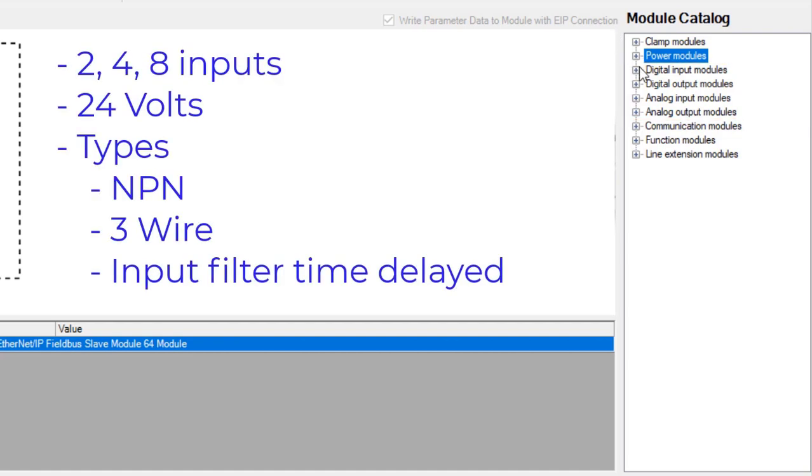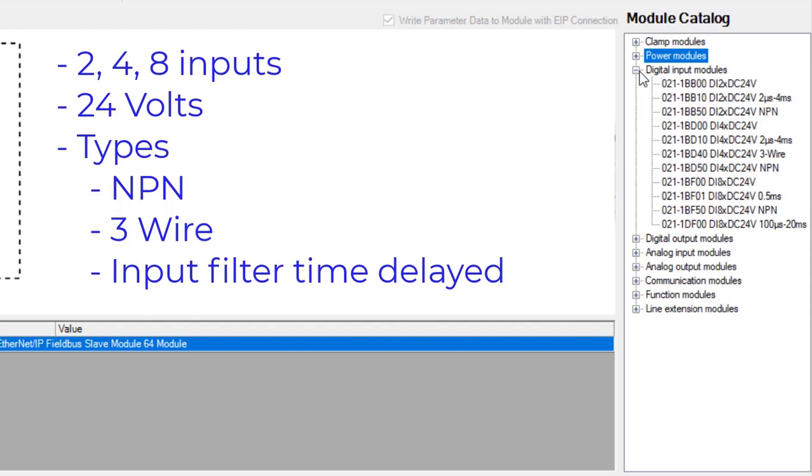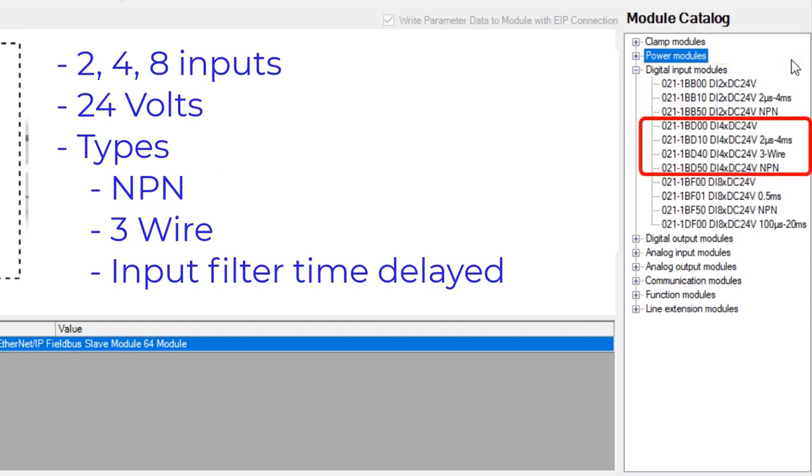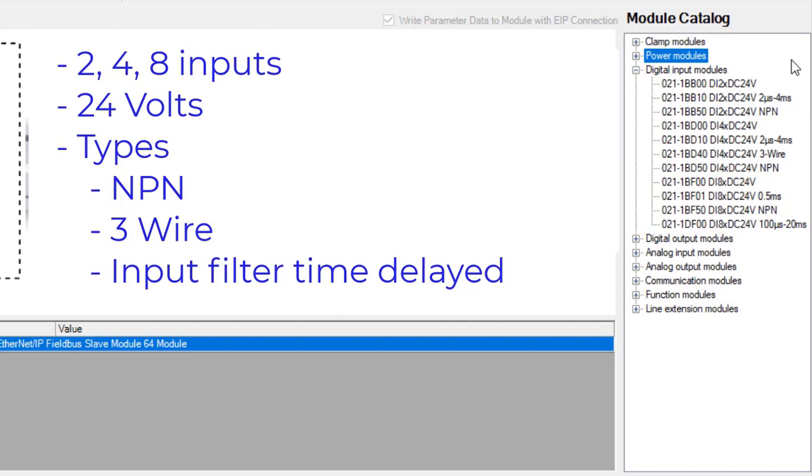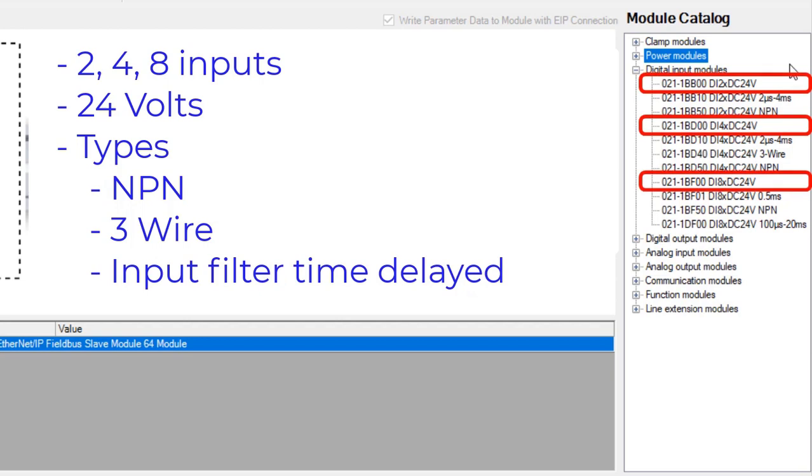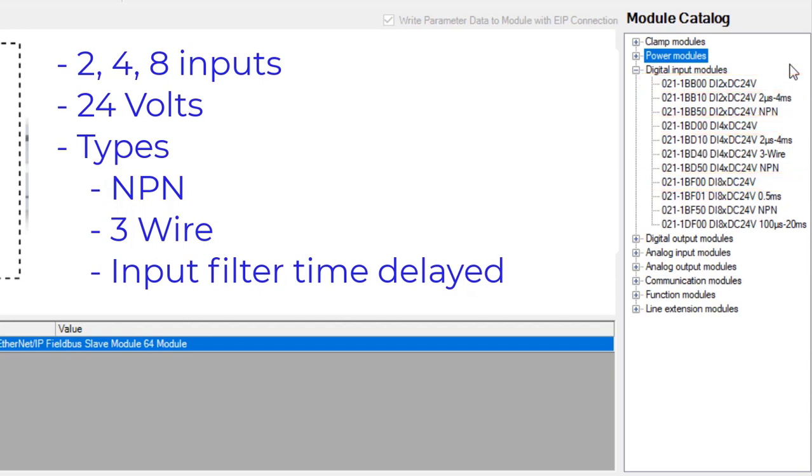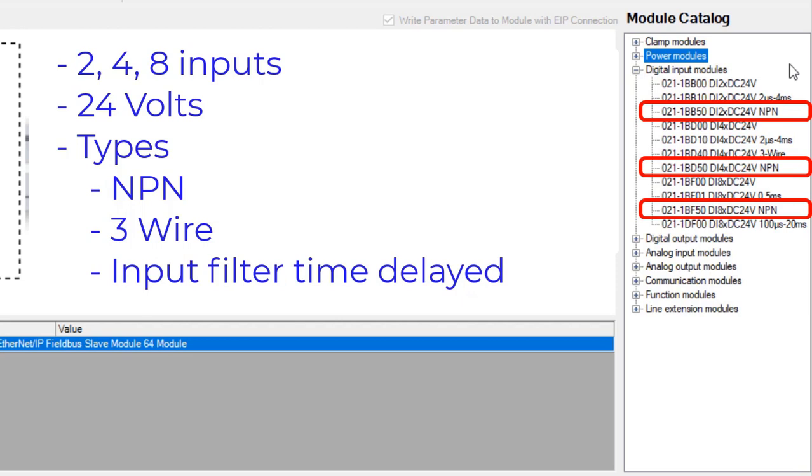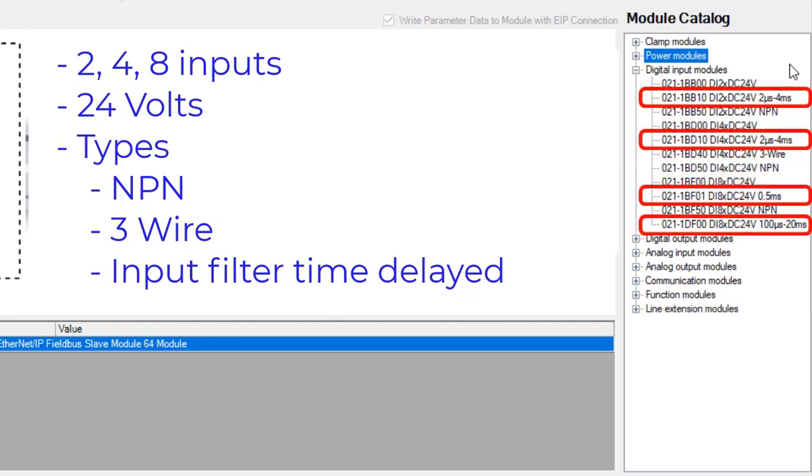Signal modules are your basic digital and analog input and output devices. Looking at the digital input slices, there are 2, 4, and 8 input slice modules that work with 24V input devices. There are slices that can be either PNP, voltage sourcing inputs, or NPN, voltage sinking inputs. Some slices have an available filter built in for time-delayed inputs.